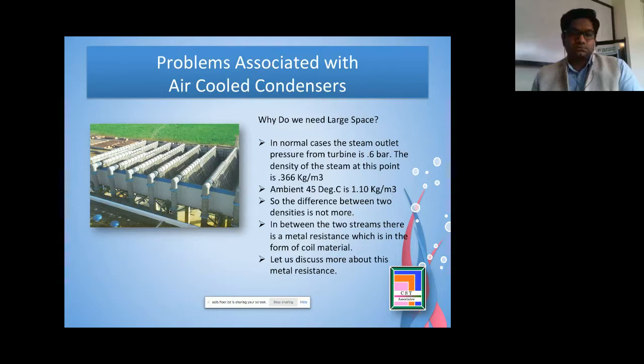Then, what is the problem with the ACC? In normal cases, steam outlet pressure from the turbine is 0.6 bar. The density of the steam at this point is 0.366 kg per cubic meter. At an ambient air temperature of 45 degrees centigrade, the air density is 1.1 kg per cubic meter. So try to understand two things. We have almost air on both sides. The steam is there, which is like a dense air, and the air on the outside is also air. So we are trying to cool air with air, so we definitely need a very big area, because the density difference is not there.